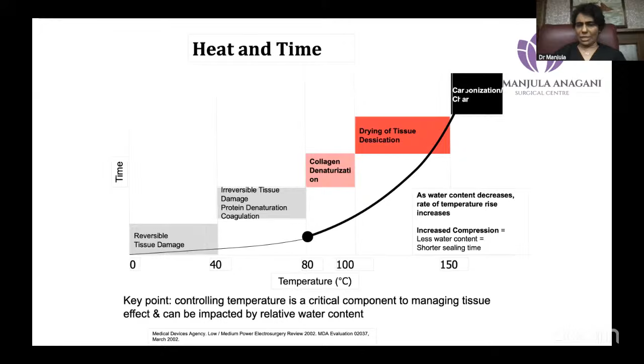Whenever we want to do laparoscopy, we want it to be in desiccation. After 150, it suddenly goes up to 400 degrees, causing carbonization or charring. We don't want that to happen, and less time is taken to become charred after 150. So our aim is to keep the temperature between 80 and 150. Advanced bipolars keep it around 100. In our traditional bipolars, we have to try to keep it at 100 to 150. How to achieve it, I will tell you.